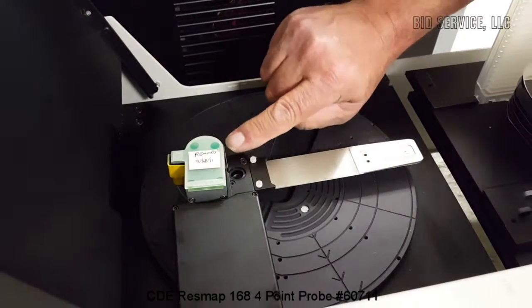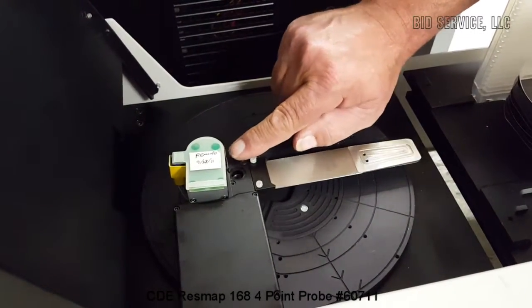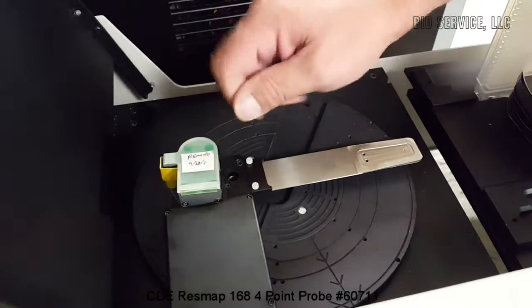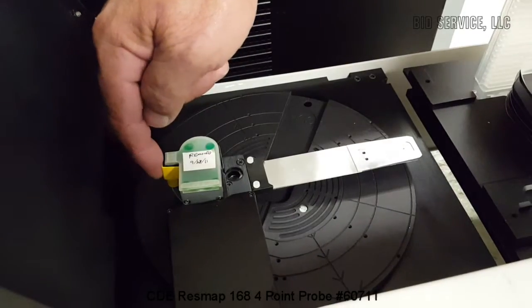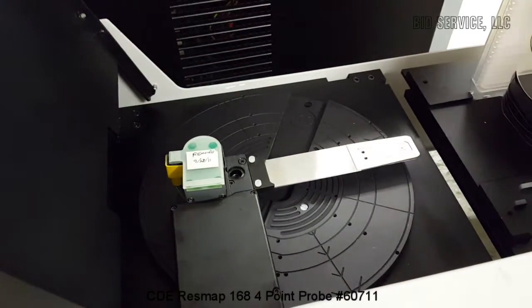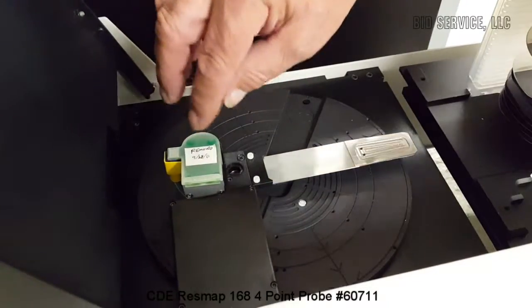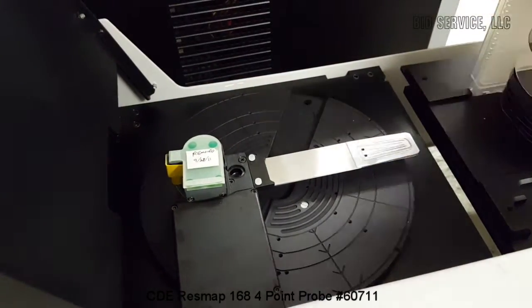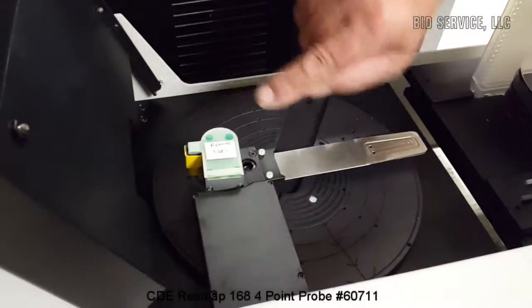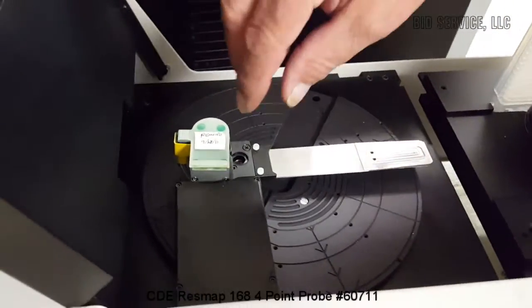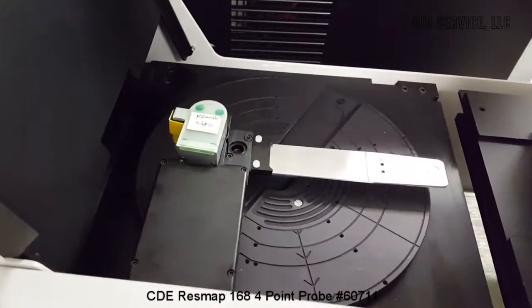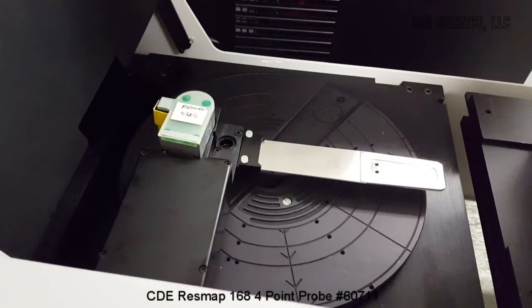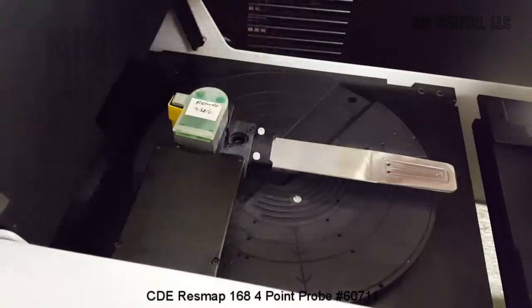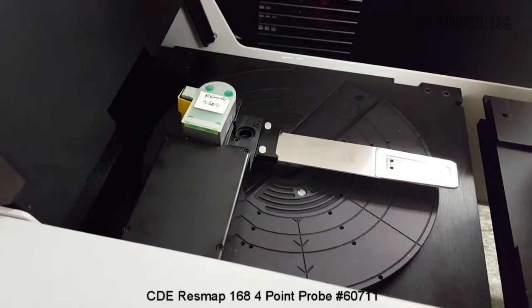It's held on with an Allen screw that goes through here. So you would loosen this up, the probe would pop out, and there's a connection here for the probe electrical connections. This probe will be removed and packaged for shipping, so you'll need to reinstall it. Just push it in so that it seats fully, tighten up the Allen screw, and that should be all ready to go. There's no alignment procedure except for the fact that it sits fully into the holder.